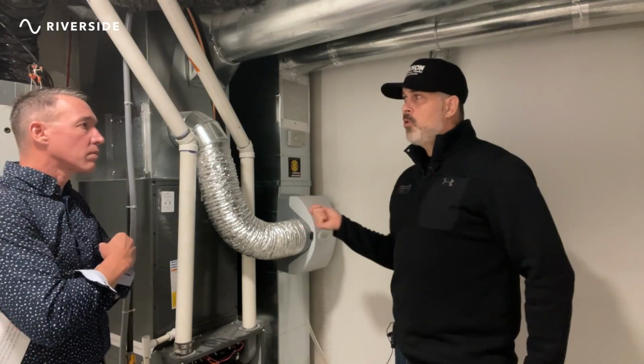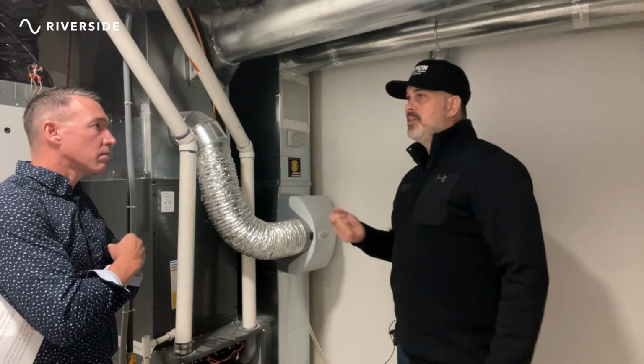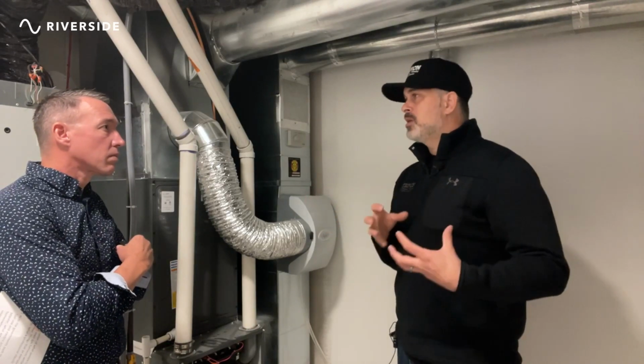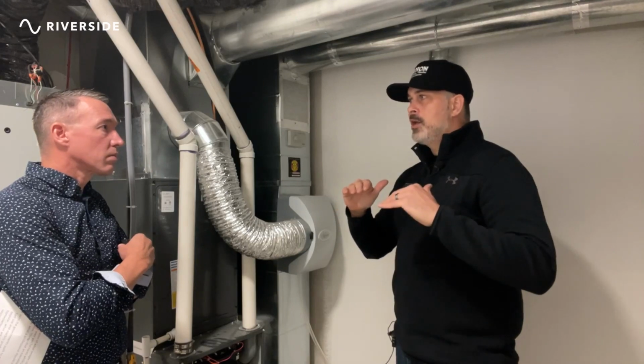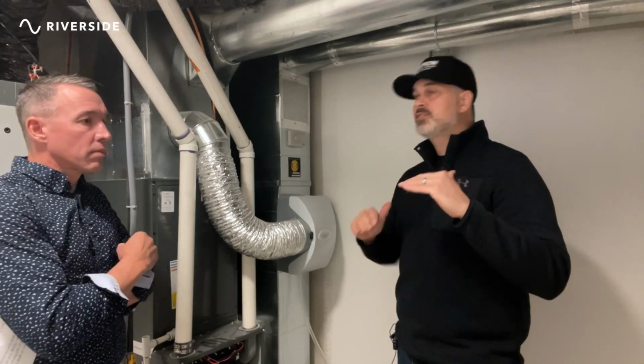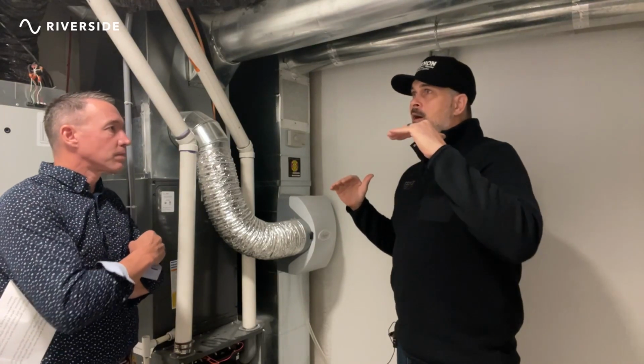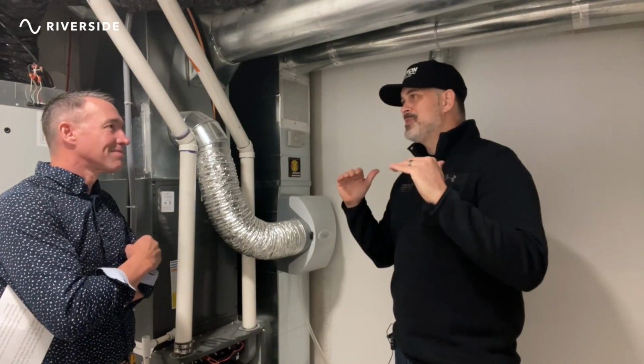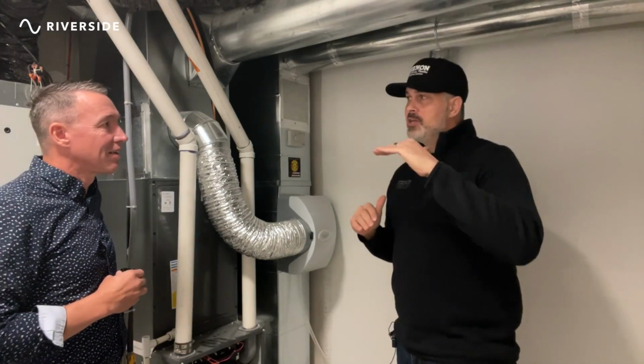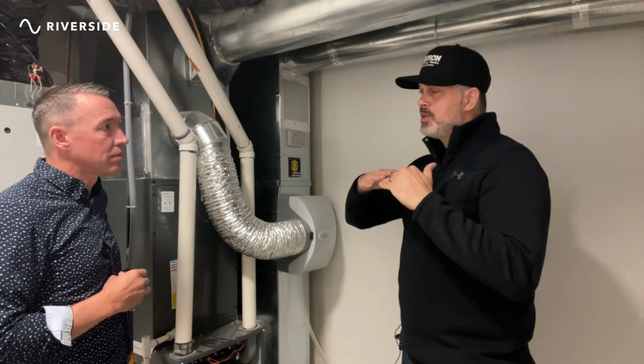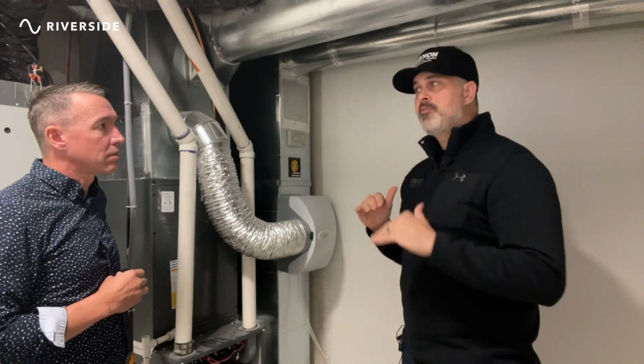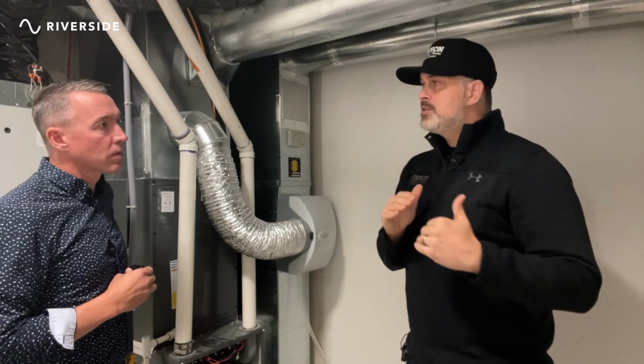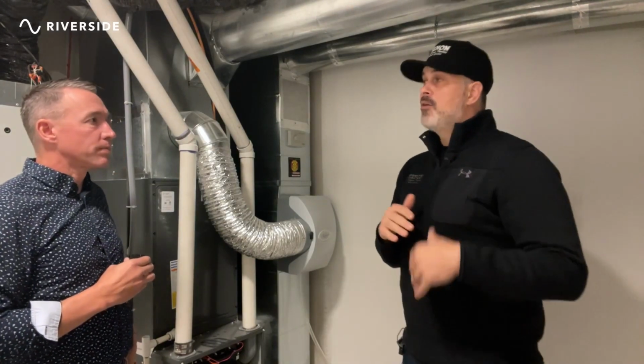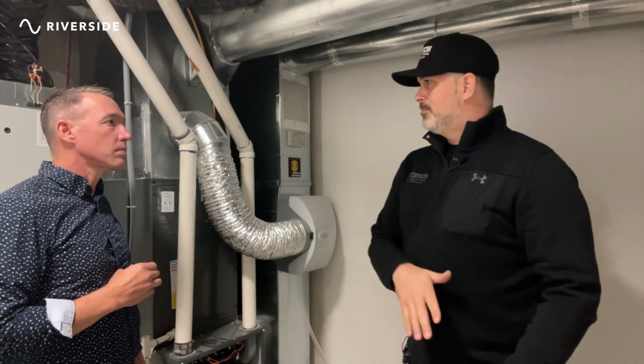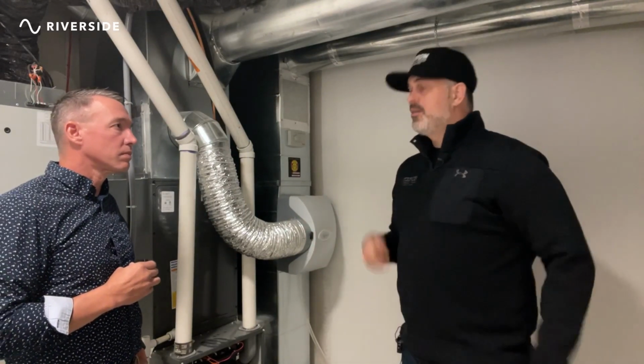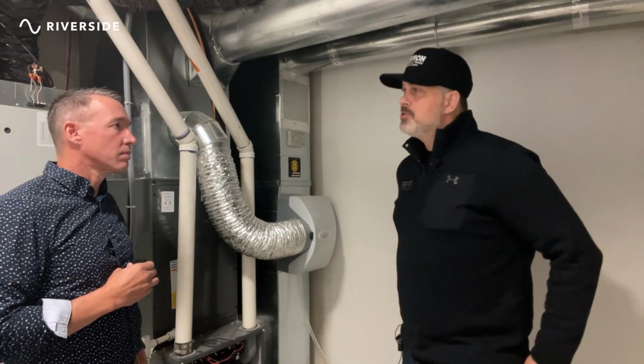Now, the big pro of a heat pump is that efficiency—the technology in them is incredible, extremely efficient. The challenge, the con, is when you look at the price of fossil fuel or natural gas versus the price of hydro. What we're told, using Fortis BC data, is that 2 degrees is the balance point, where heating your house down to 2 degrees with a heat pump is more cost effective—I'm talking cost, not efficiency. Below 2 degrees, natural gas is more cost effective. If you're heating with electricity or propane, a heat pump is always more cost effective, but if you're on natural gas, your balance point is right around that 2 degree mark.